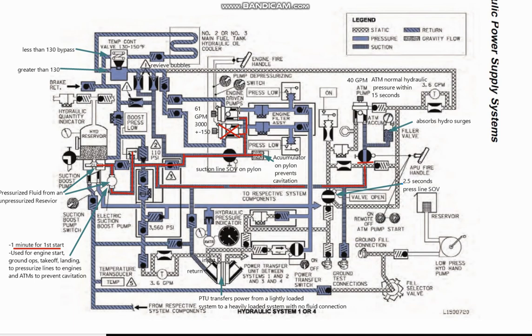Then we end up with pump pressure coming out at 3,000 psi plus or minus 150 at 61 gallons per minute. It'll come up, unseat this press low light, which will go out, and pressure makes its way through here, down, basically to the pressurized side of the hydraulic system.